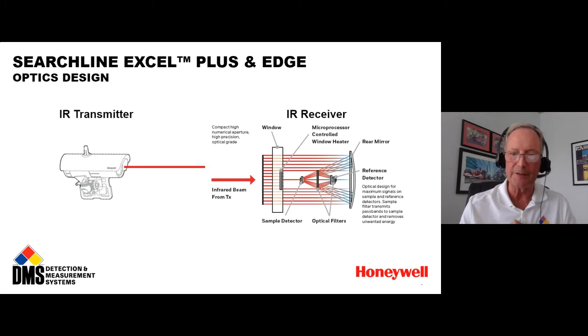So what you see is the center of the beam is red, which is the most intense portion of the beam, and then that drops off to a yellow going into a green and into blue, so it's a drop off in intensity. But you see that tight cluster of high intensity light at the center, and that's what you're looking for in terms of properly shaping the IR beam from an open path detector, because that's maximizing the light intensity at the center where it needs to be.